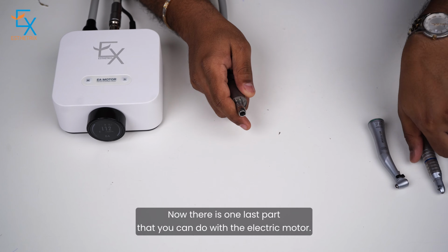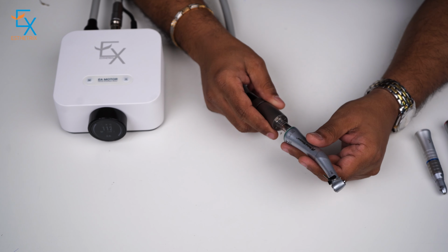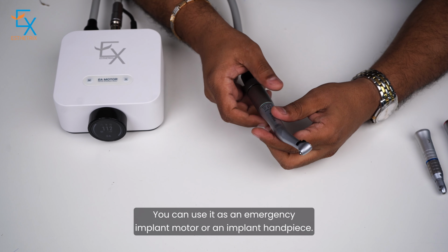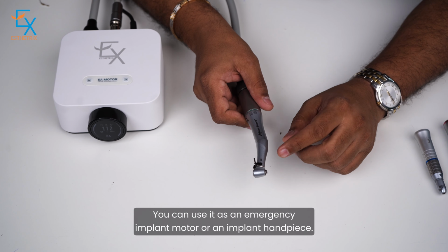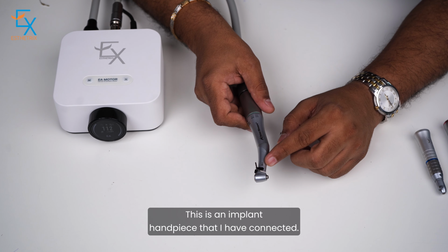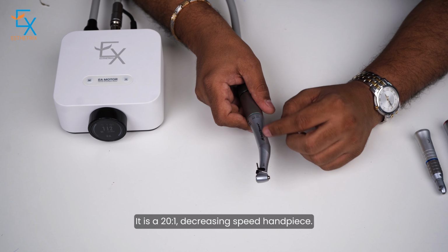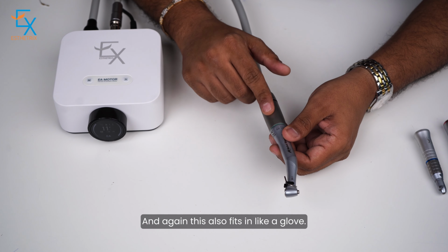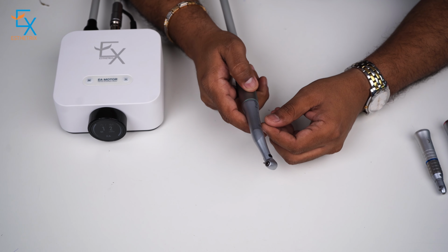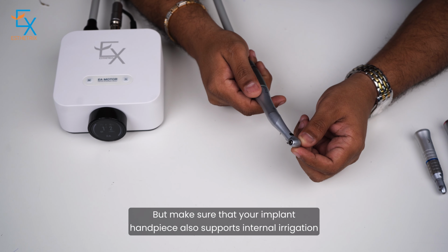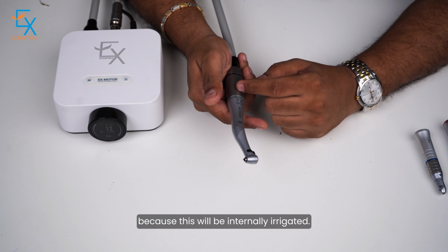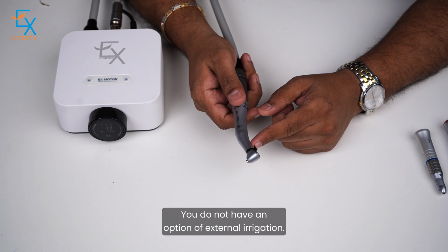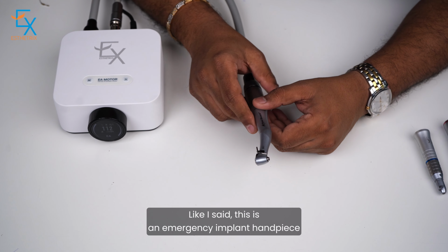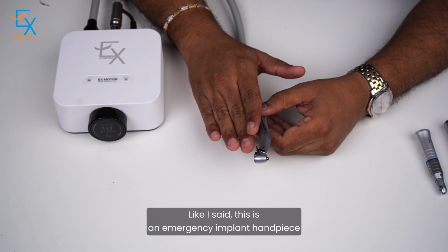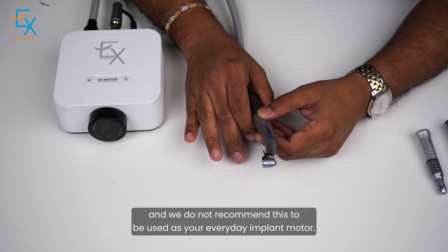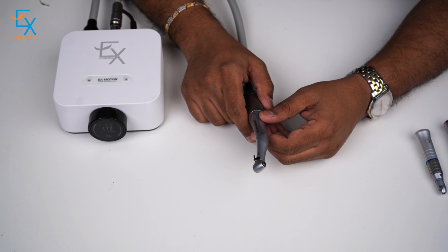Now there is one last part that you can do with the electric motor. You can use it as an emergency implant motor or an implant handpiece. See, this is an implant handpiece that I've connected. It's a 20:1 decreasing speed handpiece, and again this also fits in like a glove. But make sure that your implant handpiece also supports internal irrigation, because this will be internally irrigated. You do not have an option of external irrigation. So, like I said, this is an emergency implant handpiece and we do not recommend this to be used as your everyday implant motor.